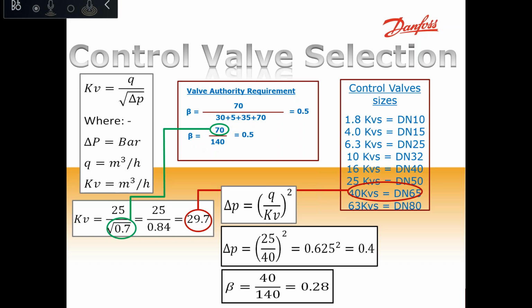Now, if we take most of the old projects, they would recommend a two-way valve on-off on FCUs and a modulating actuator on air handling units. Why? Because there is no use of the modulation on the FCUs if you have a very poor authority, because even if you put a modulating actuator with an authority of 0.2, you will end up acting like on-off because the valve will be oscillating up and down due to the system pressure. So from this, we can understand that system pressure is key to the proper selection of any valve, and we have to consider that.